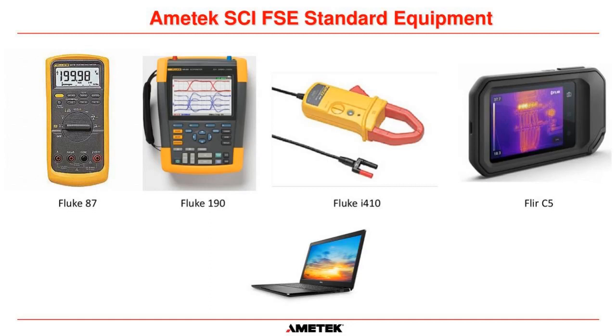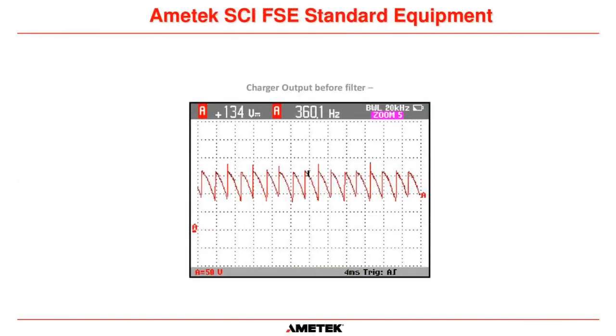As discussed earlier, they carry a FLIR C5 thermal imaging camera, and they all have a laptop so they can connect to each of those devices as necessary. And the reason why it's important for an oscilloscope to be used when performing maintenance is we're looking at waveforms within the UPS. Now, here's a prime example.